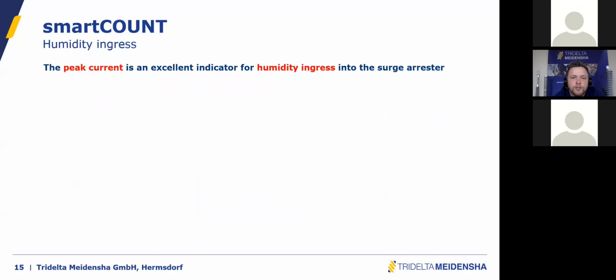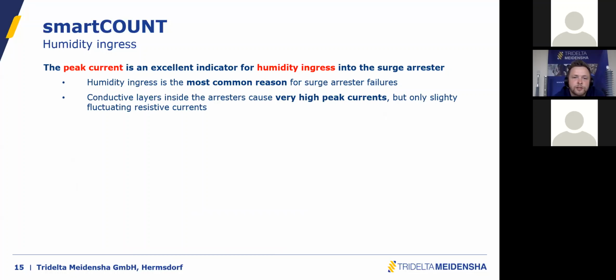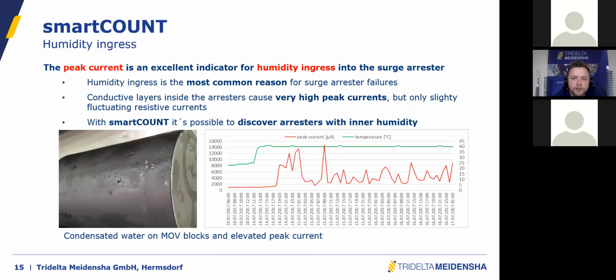Second failure mode, humidity ingress. Therefore, we need the peak current to indicate this failure mode. Humidity ingress is the most common reason for surge arrestor failures, because conductive layers can appear inside the surge arrestor, and they will create high peak currents, which are somehow fluctuating and not steady. And I will show you how we measure that with the smartCOUNT.